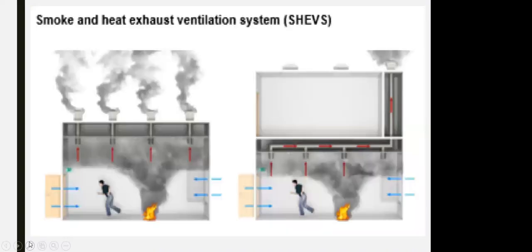Mechanical ventilation, so we have to mechanically extract the smoke outside. It has many arrangements for the system, depending on the architect and the space arrangement, depending on the space above the false ceiling, how many extract fans, and how many locations you can extract the smoke from. In many cases, like the first one, we extract the air by adding smoke fans on the top, each one a standalone vertical unit. Or you can make it ducted and collected from the smoke exhaust up to the ceiling itself.